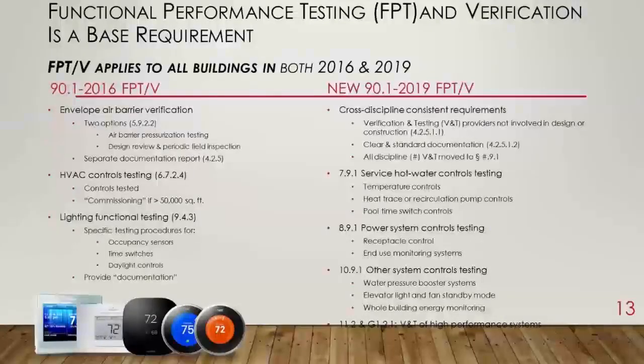Now, this is an eye chart situation, but it gets into some of the details. Again, what was required as far as functional testing and verification in 2016, and then over on the 2019 side, again, we added service water heating controls testing so that the temperature controls would be verified to be there and set up properly. Any heat trace or recirculation pump controls would be verified. There's also some pool time switch requirements. Those would be verified as well.